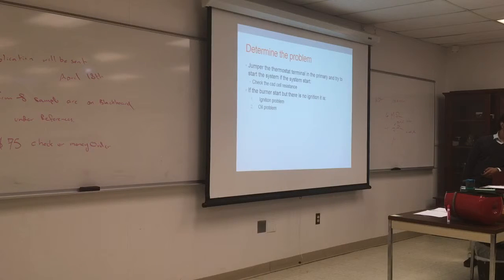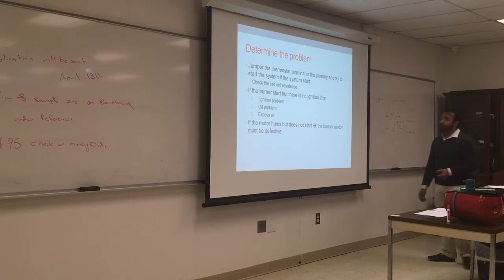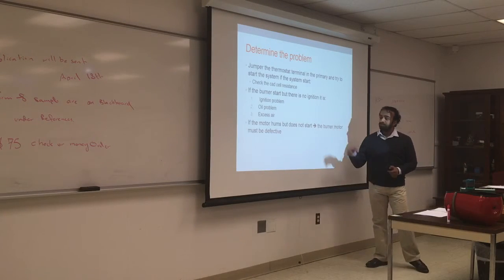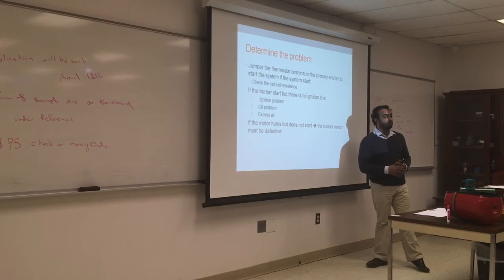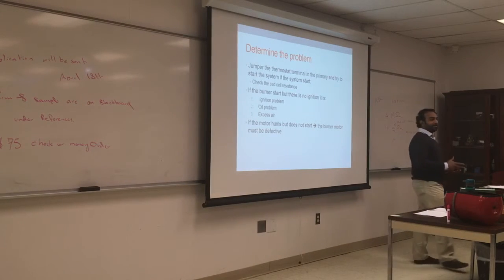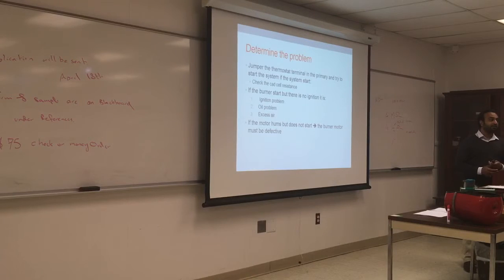What if it starts and goes away? Could still be an oil problem. Excess air: if you have too much air, the air might be blowing off the fire. So if you have too much air, probably it's an issue, so you have to choke down on the air intake. If the motor hums but does not start, could be the burner motor is defective, or could be the capacitor. Smaller motors, you have a capacitor, the capacitor gets dented or bulged, and they could be faulty.